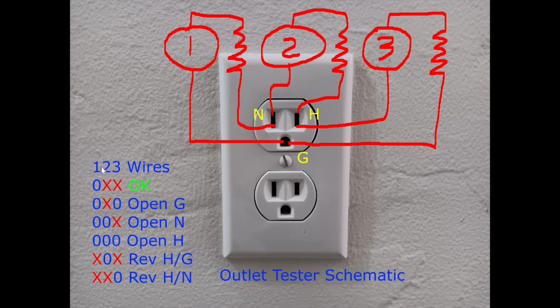And then using this chart, if for 1 you get 0 volts and 2 you get 120 volts, which is indicated by this X, and 3 you get 120 volts, which is indicated by this X, then the wiring is okay. If not, you go by this chart. It could be open ground, open neutral, open hot, reverse hot ground, or reverse hot neutral.